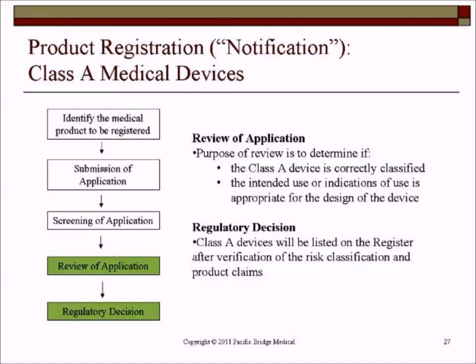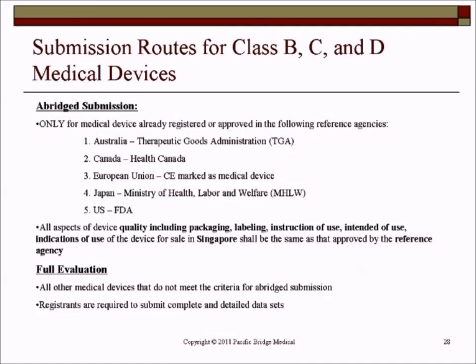Okay, the abridged submission - as I said, these are the five countries to take note of. I'd like to point out that HSA requires the company submitting the abridged submission to decide on one country of choice. That means if you have approval in Australia, Canada, and the US, you need to decide which of those countries you want to base the abridged submission on. When you base the abridged submission on a country, you need to ensure that the packaging, labeling, IFUs, and intended use are the same as in that country of choice. If they are not the same, you would need to choose the one you want to submit. This is something important to consider when making that decision.